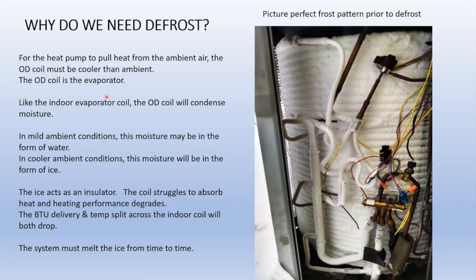So why do we need defrost? Well, in order to absorb heat energy from outside, the outdoor coil has to be colder than ambient to absorb that heat energy. In many cases, that means the outdoor coil is going to be below freezing and you're going to develop frost on it. So this is a picture of a perfectly frosted unit, likely just about to enter a defrost cycle.